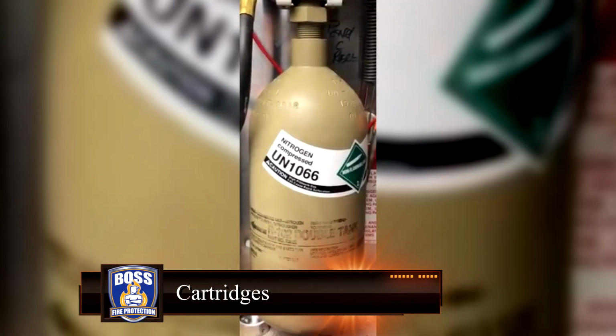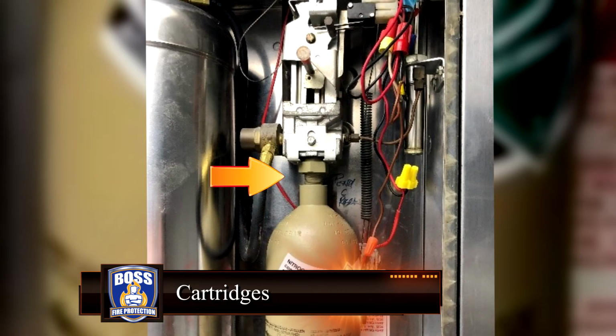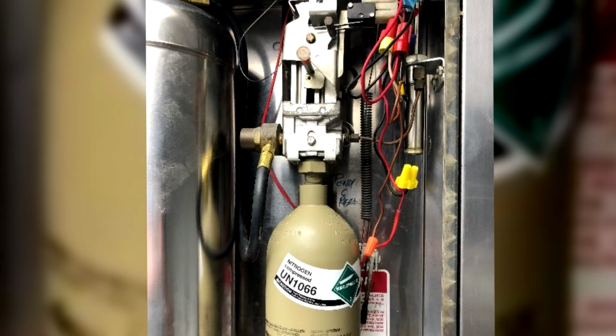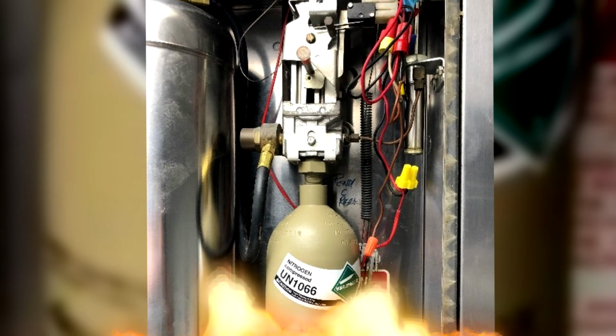Cartridges tie into the regulated release, which is made to puncture the seal of the cartridge upon actuation and fill bottles with compressed air. This sends chemical through the system piping. Cartridges must be changed out or hydro-tested every 12 years by DOT specifications. This should be inspected and maintained by your fire suppression inspection company.